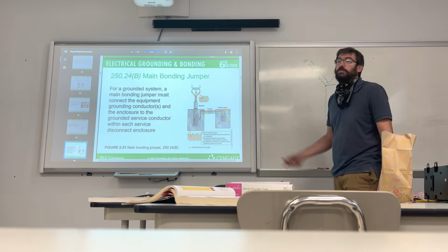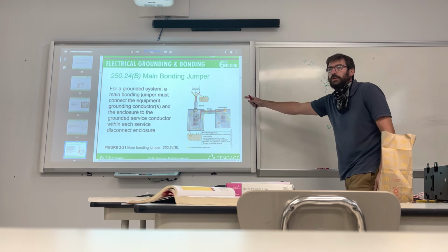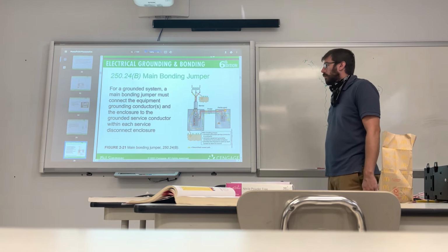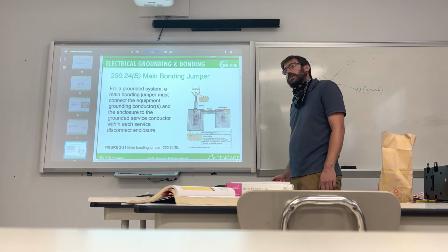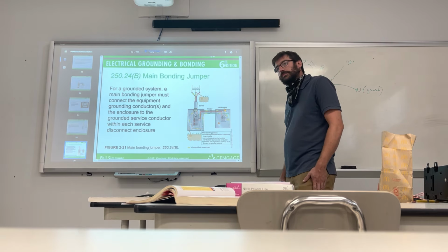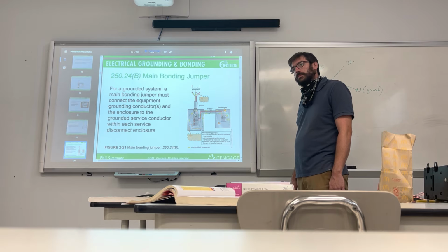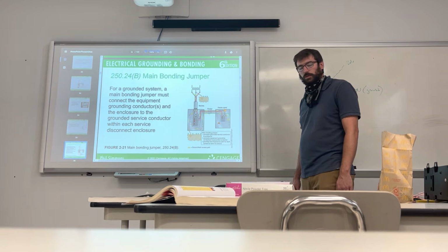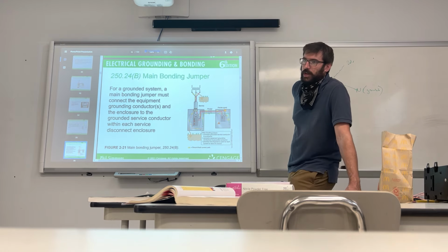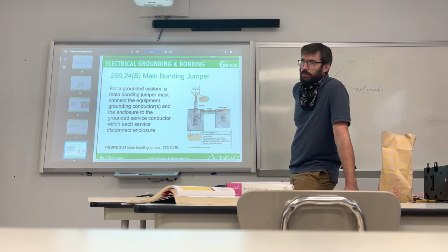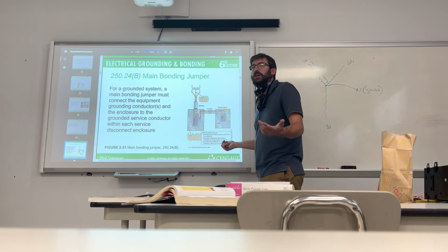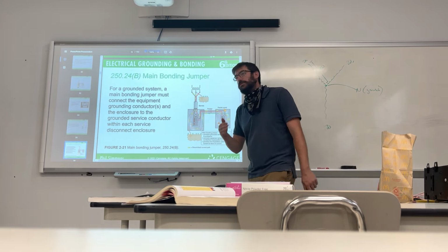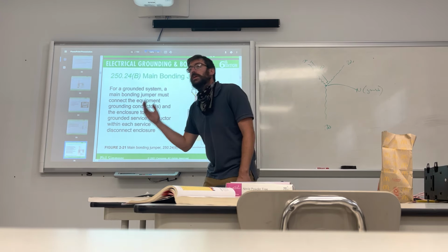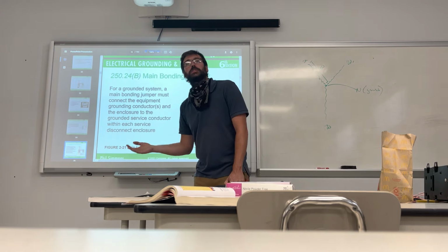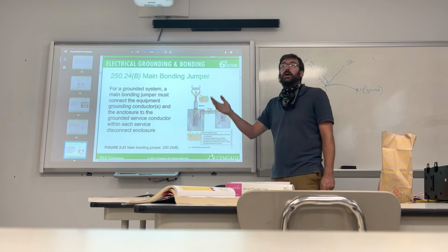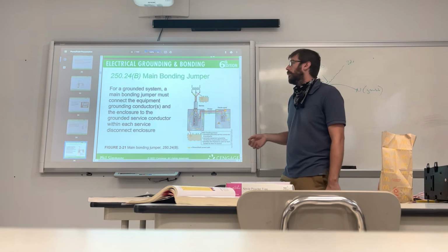Should it be as thick as the hot conductors though, right? No, but you should reference how thick the incoming conductors are. You don't have to make the bonding jumper the same size, because it only carries current for a couple seconds. So how would I figure out how big to make that then? Referring to the NEC. Oh, okay, cool. You see how easy that was? It's just looking up a chart. You have 600 amps coming in, your ground has to be this size. Like I said, I don't expect you guys to know all this information off the top of your head, but I do expect you to know where to look. All right?